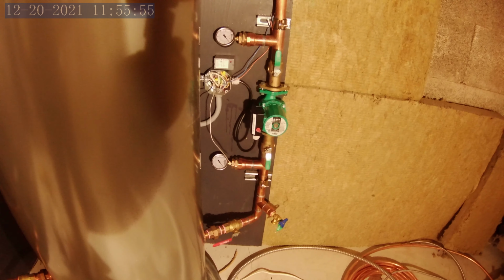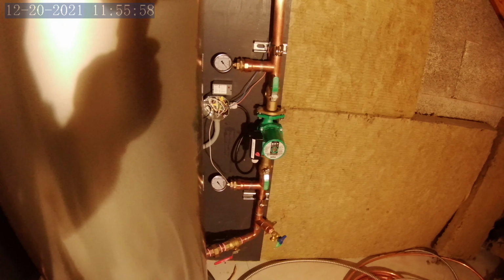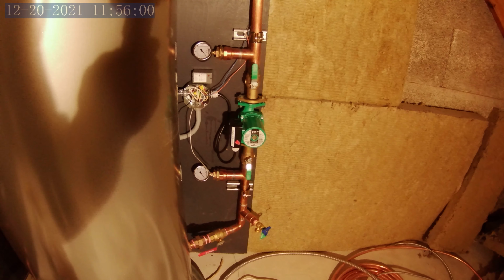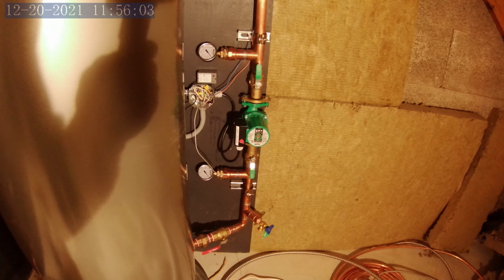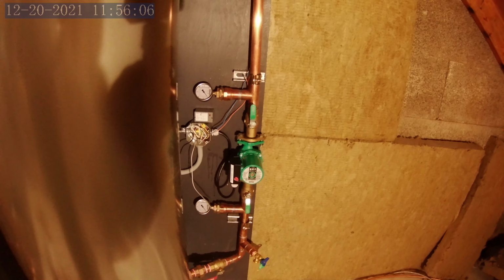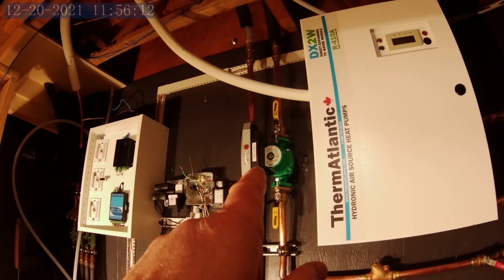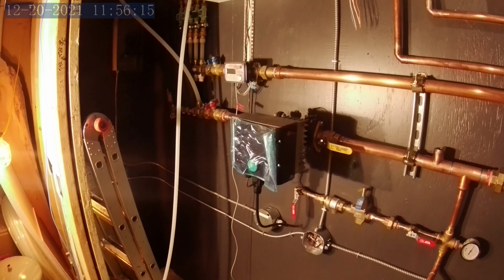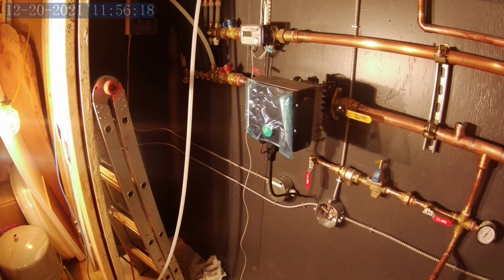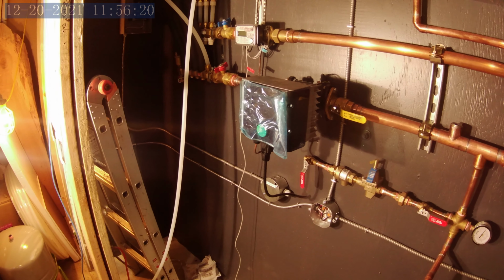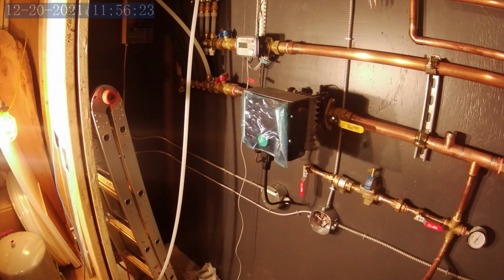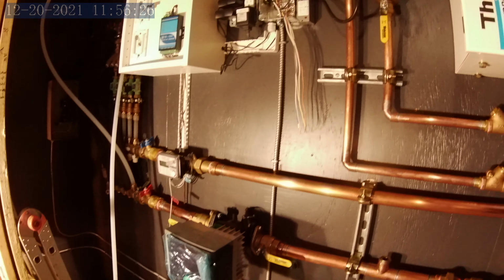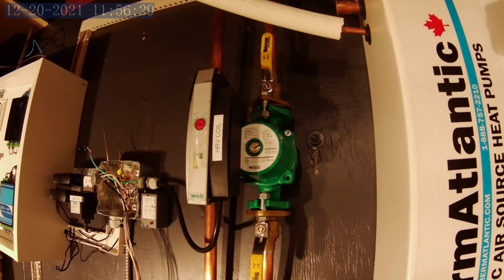And the valves on each side will help us determine the pressure drop, and that, I believe, helps us to determine the flow. But basically this will be a fixed speed circulator. The HRV coil will be a fixed speed circulator, and then the Wilo Maxo will be a variable speed. It will ramp up and down as required to maintain pressure and flow. The HRV is a Wilo Stratos Eco, and the heat pump tank is a Wilo Star.